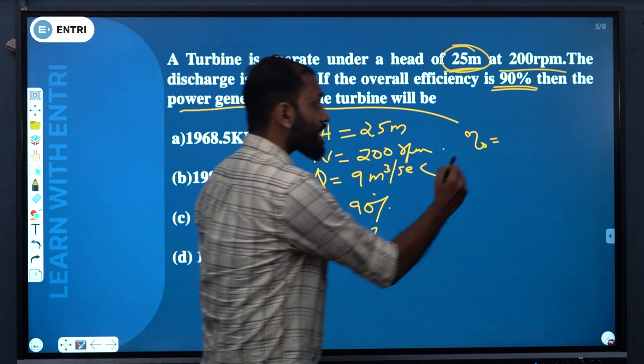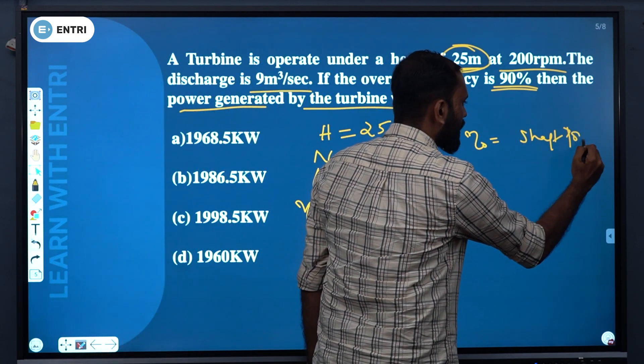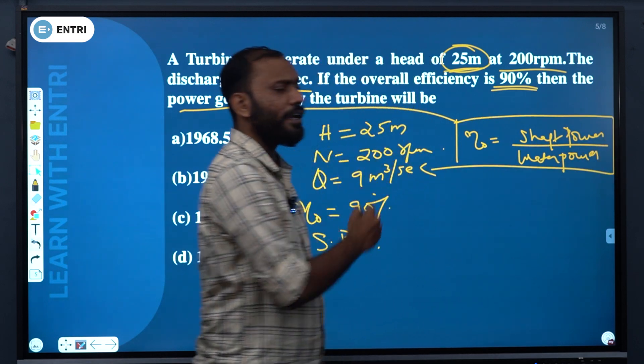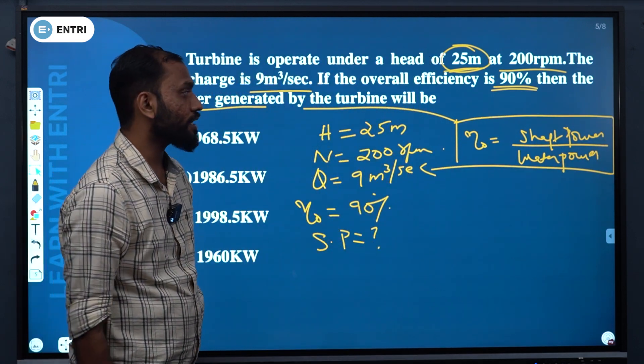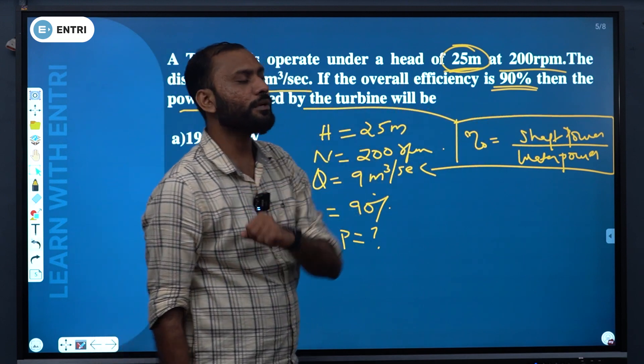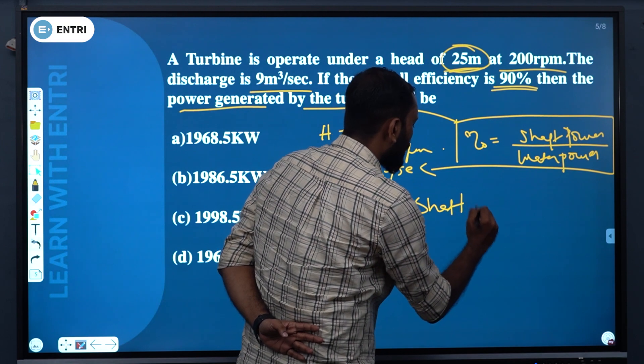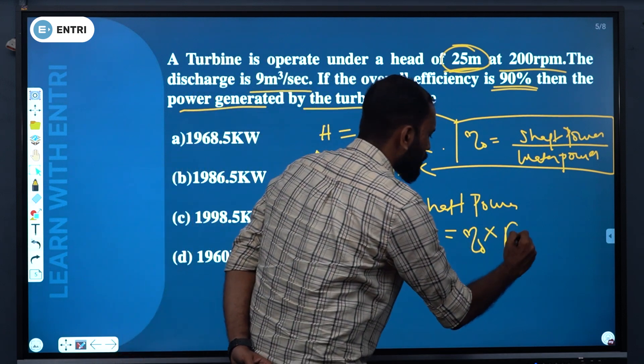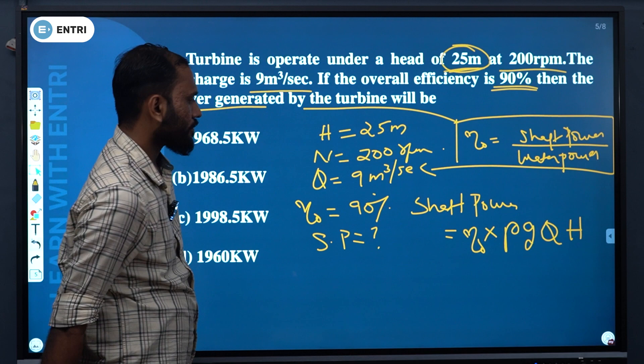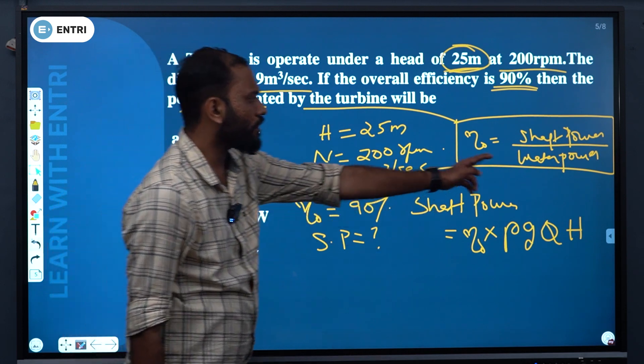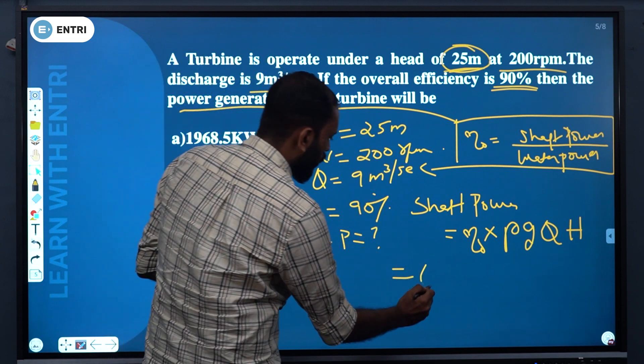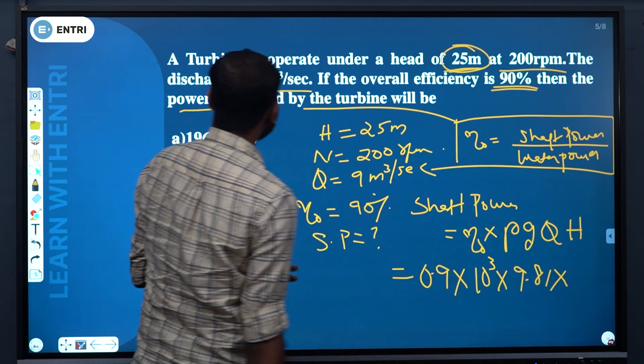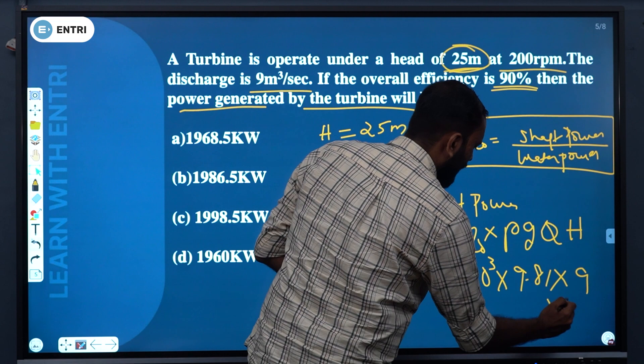Overall efficiency is defined as the ratio of shaft power to water power. Shaft power is given by the equation: overall efficiency into water power, which equals rho × g × Q × H. So, shaft power equals 0.9 × 10³ × 9.81 × 9 × 25.